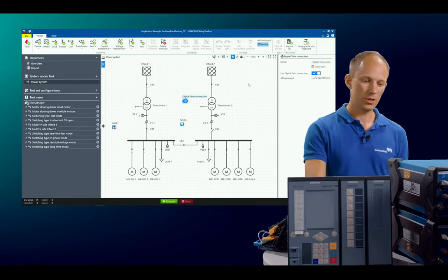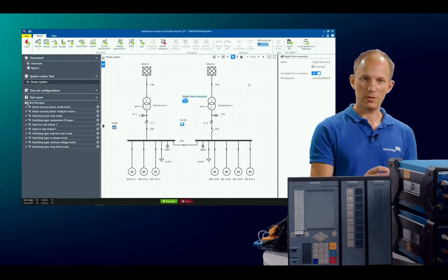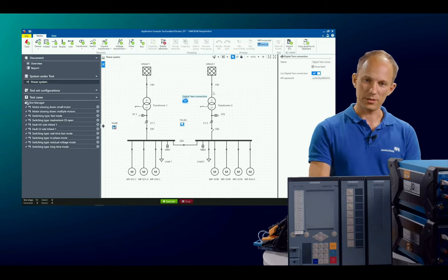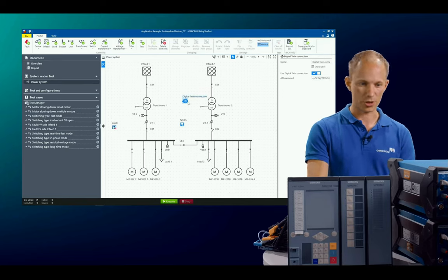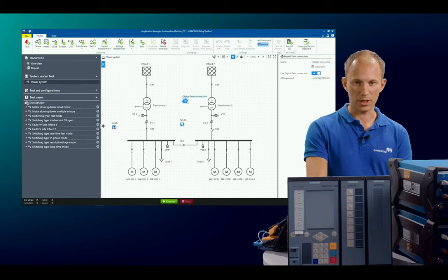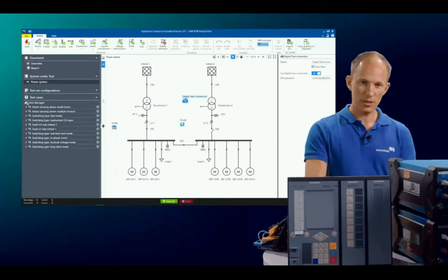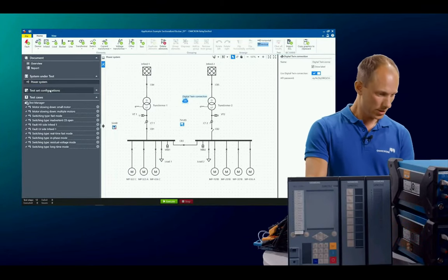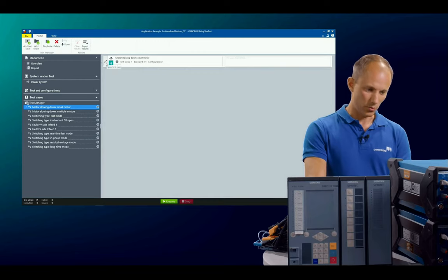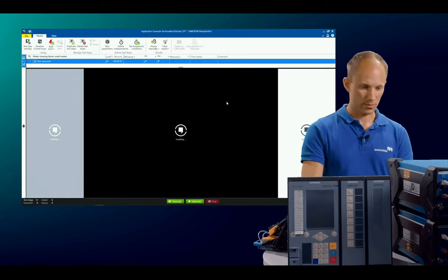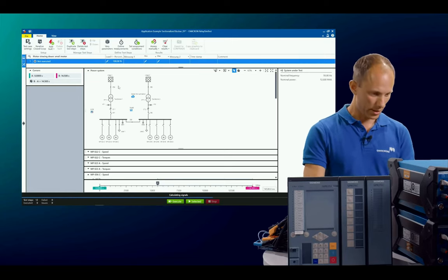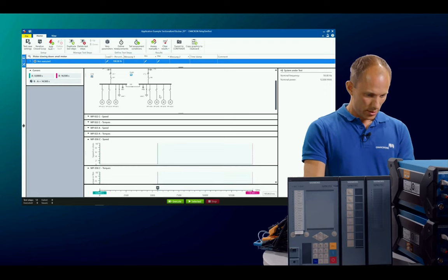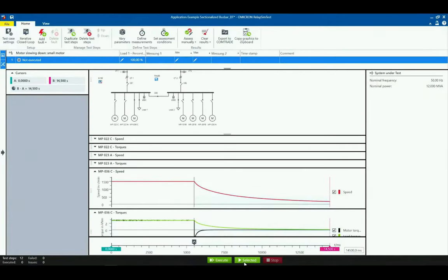So as I have told you, just use exactly the same test file, insert this digital twin connection, and then you can run all the tests you have prepared with the SIPROTEC digital twin. I will show step by step how that works. So I inserted this digital twin connection. The hardware disappears and I can start with my test cases as I'm used to. I can also simulate different cases there.